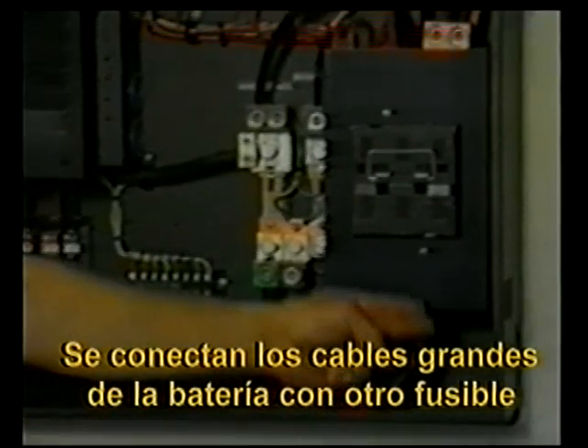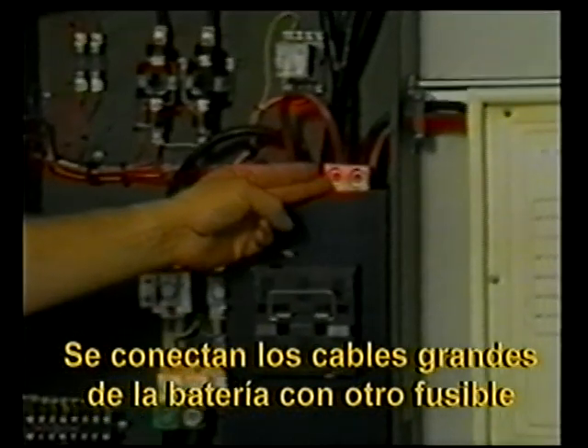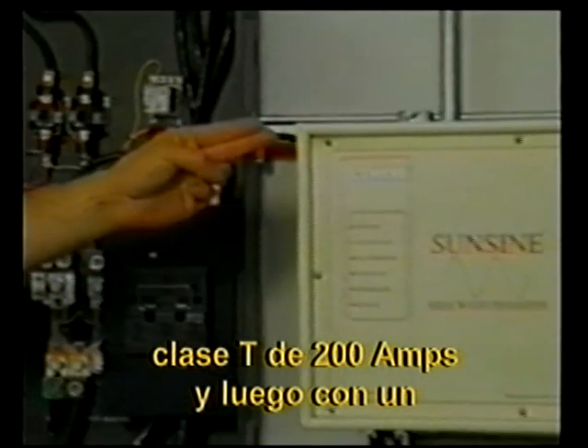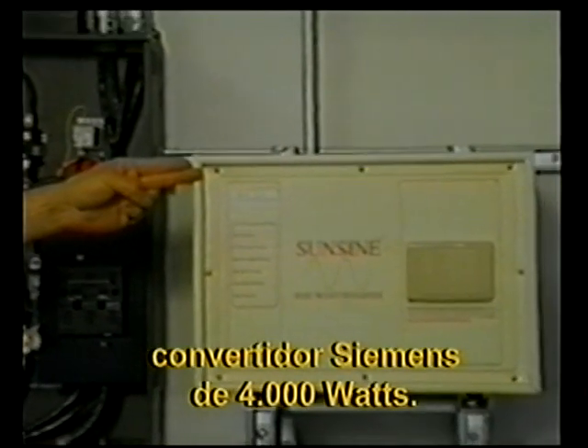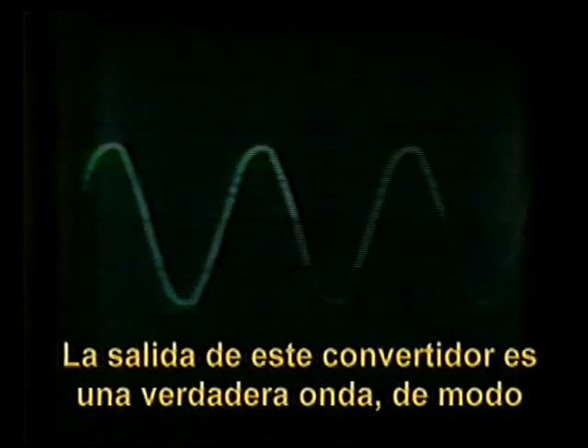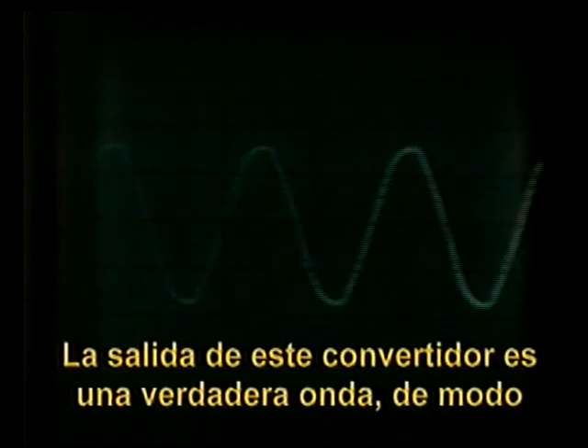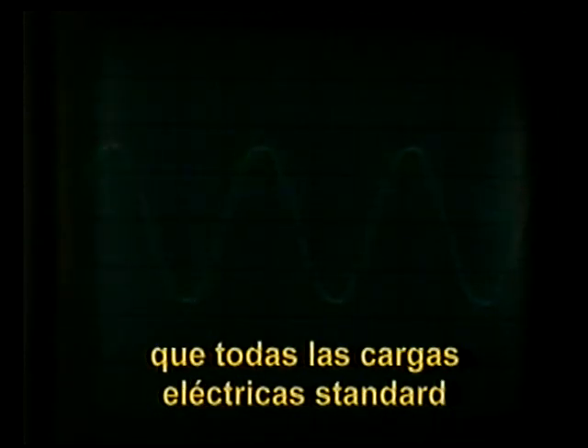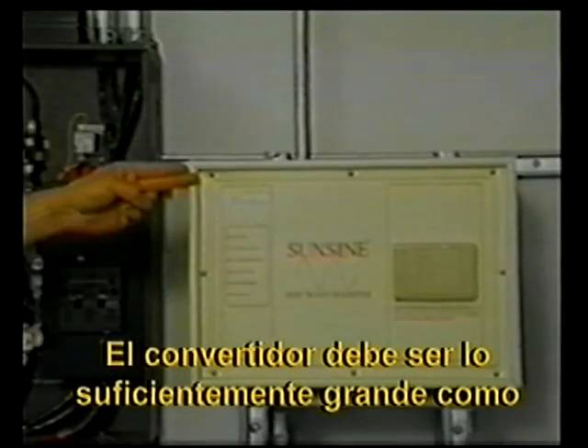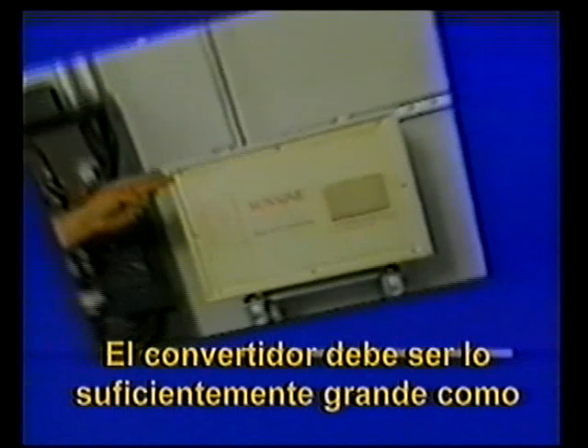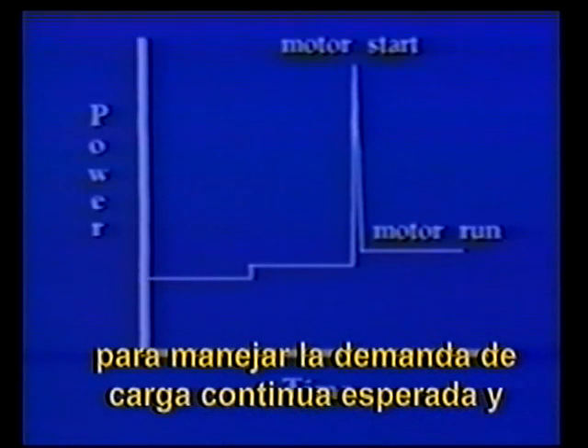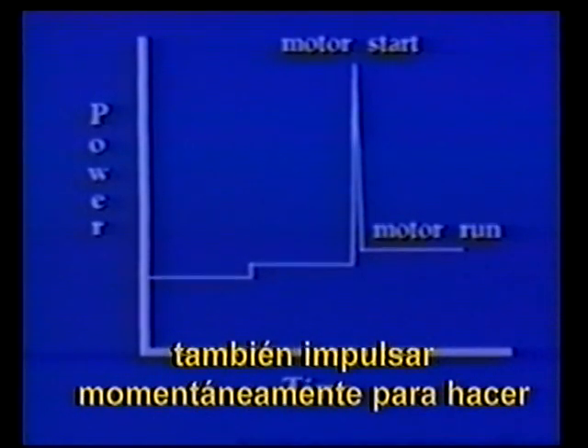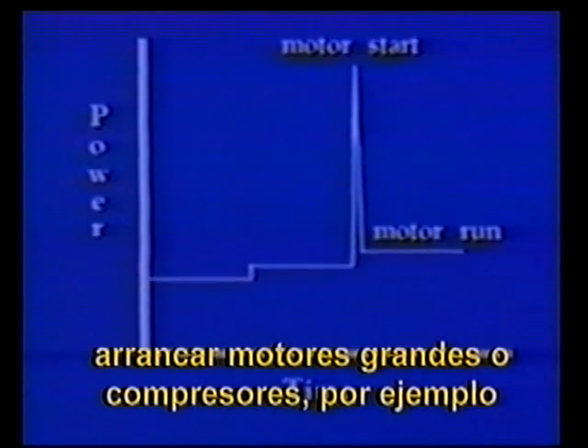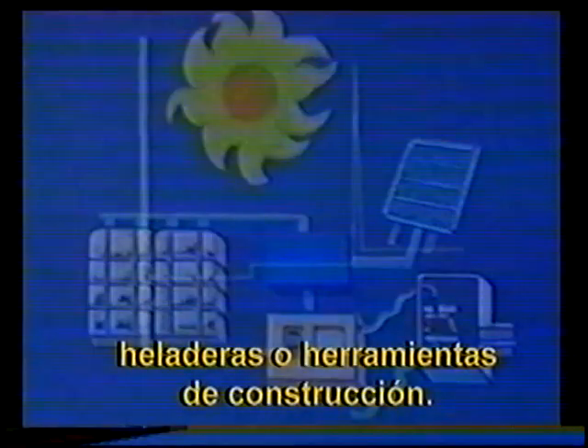Large cables from the battery are connected to another 200 amp Class T fuse and then to a 4,000 watt Sunsine inverter. The output from this inverter is a true sine wave, so all standard electrical loads will operate without any problems. The inverter should be large enough to handle the expected continuous load demand and also surge momentarily to start large motors or compressors, for example, in refrigerators or construction.